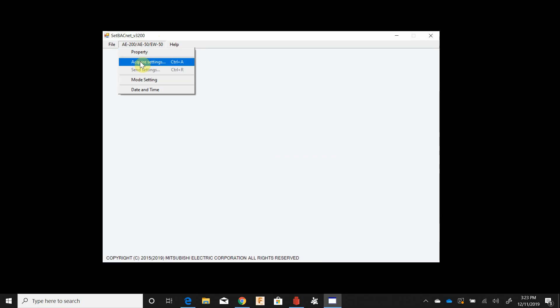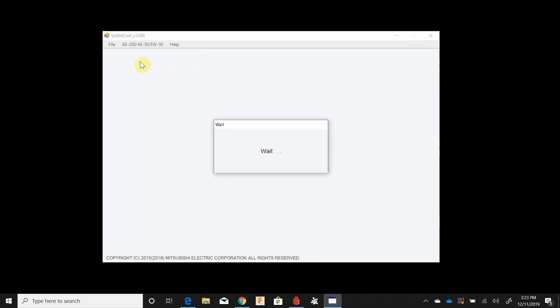Then we'll go ahead and acquire settings. This is going to pull the settings that we already have in here. These are going to be defaults. This LAN 2 can be set from here or set through the touchscreen on an AE-200. Our BACnet port number 47808, leave that at default unless told otherwise by the system integrator.